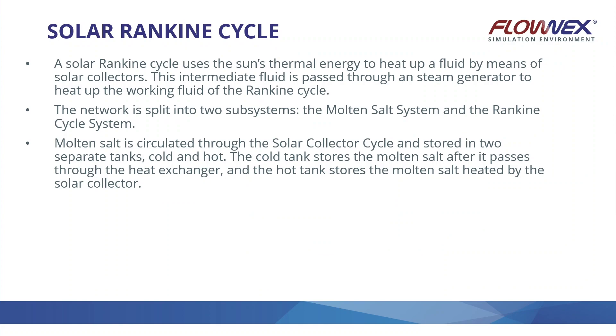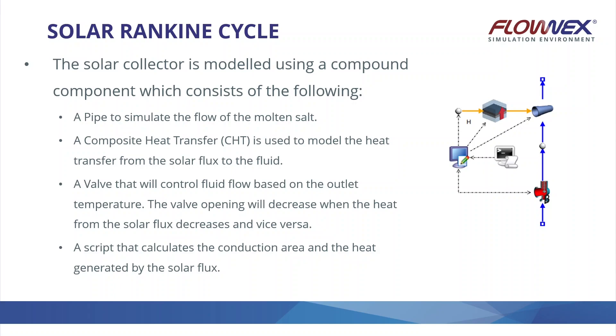A Solar Rankine Cycle uses the sun's thermal energy to heat a fluid via a solar collector. The intermediate fluid passes through a steam generator to heat the working fluid of the Rankine cycle. When simulating, we split the network into two subsystems: the molten salt system and the Rankine cycle system. The molten salt is circulated through the solar collector and stored in two separate tanks — a cold tank and a hot tank. The solar collector is modeled using a compound component in Flownex.